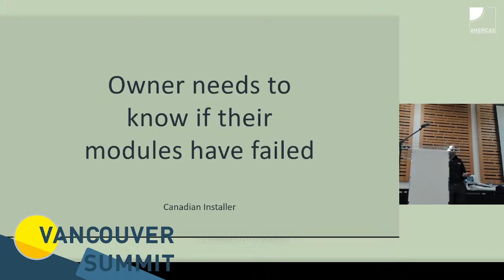Like, if as an installer, how do you know which module exactly failed? You won't know which module failed, but you will know there is a problem. And when you do know there is a problem, to find out which is your module that has failed, there's different ways to do it. You can use, I don't know, like a heat gun to find out what temperature it's running at. Maybe you have a few hot spots or something like that. But so it's basically about troubleshooting.